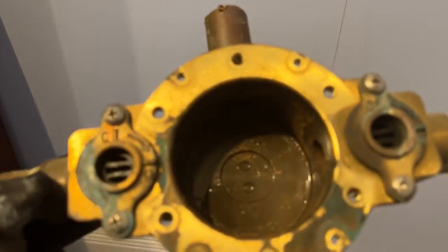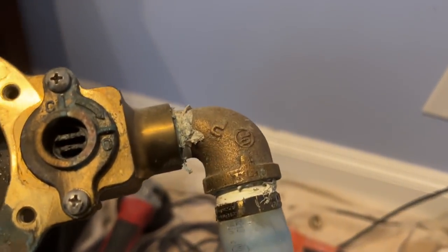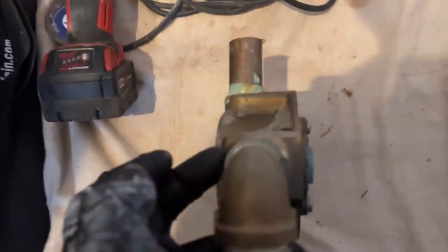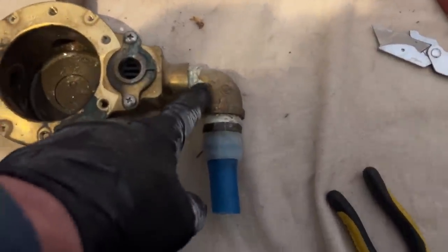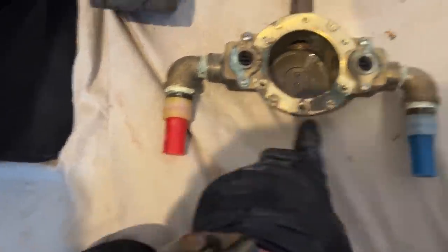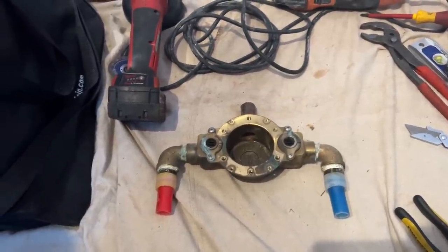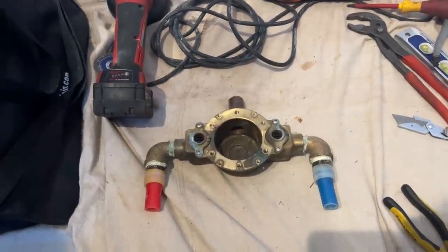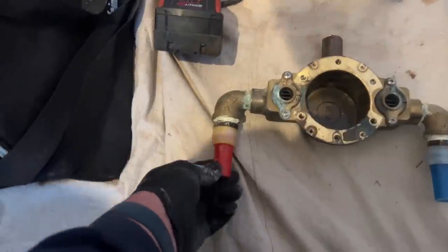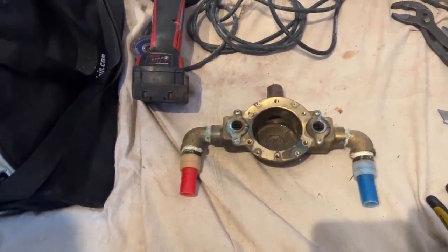Now we have to replace this. Let's take a look at what they used here. We had a three-quarter inch brass nipple that connected the thermostatic valve to the transfer valve - the diverter. We have a three-quarter inch street brass 90 there, and we have a three-quarter inch expansion PEX male adapter on both sides. If you notice, they're using the Uponor expansion PEX - three-quarters is red and that's blue. If you Google Uponor expansion PEX and then the infamous keyword at the end - the lawsuit - you will see that a party is suing them on proposed class action status because part of the manufacturing, when they put the PEX into the furnace to bake on that color, it degrades the exterior of the tubing.